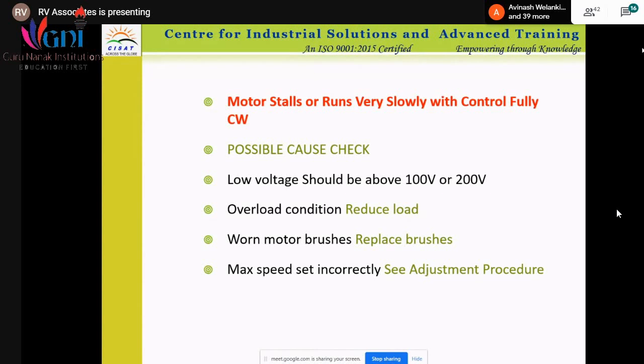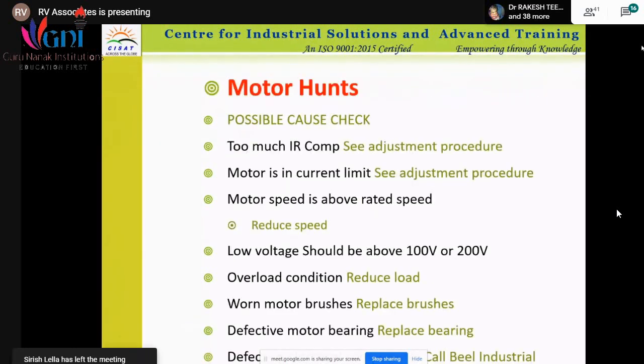Then the motor stalls or runs very slowly. Various causes can be there, like the load is more because of an overload condition, the motor is running slowly, or the motor is stalling because of harmonics. So we should know what the possible reasons are. There are a number of things available; just check one by one. Motor hunts. Why is the motor not running, or why is start-stop happening? So what are the possible checks? Like this, many faults are there in the motor.